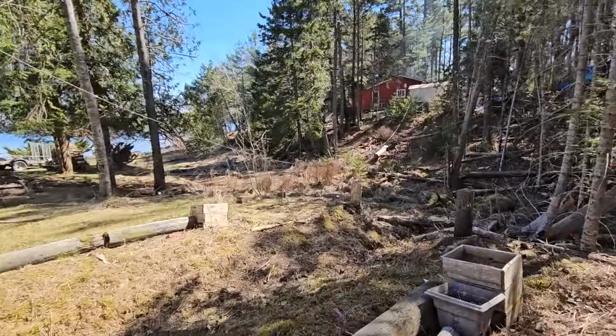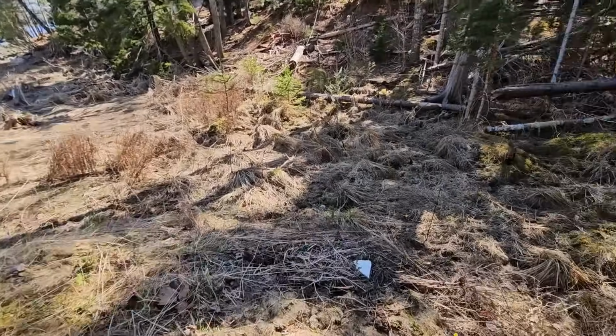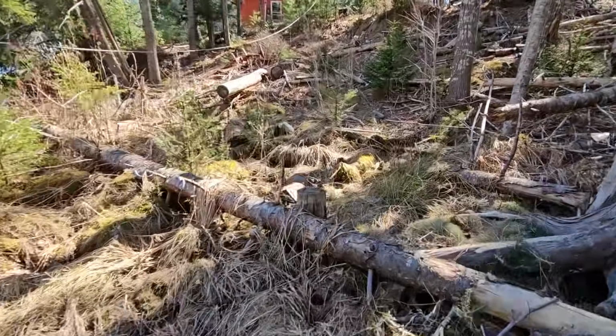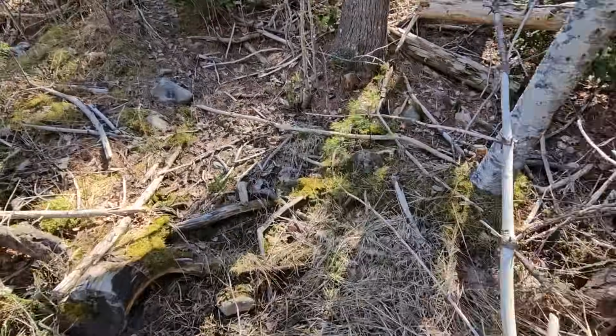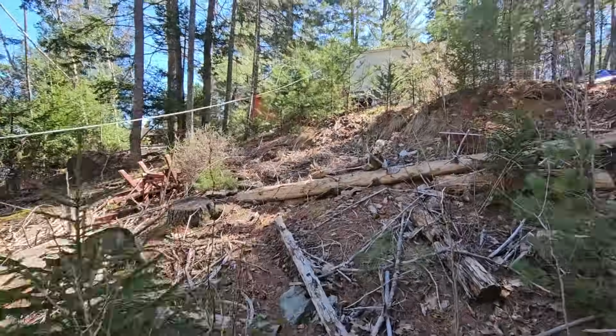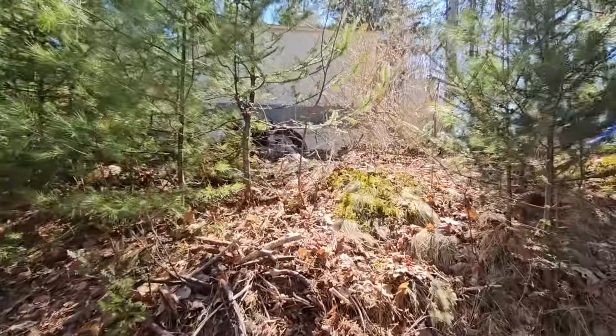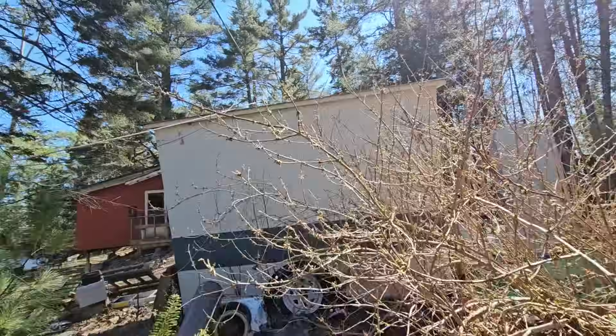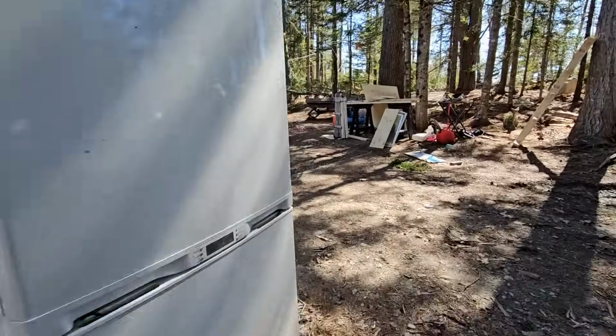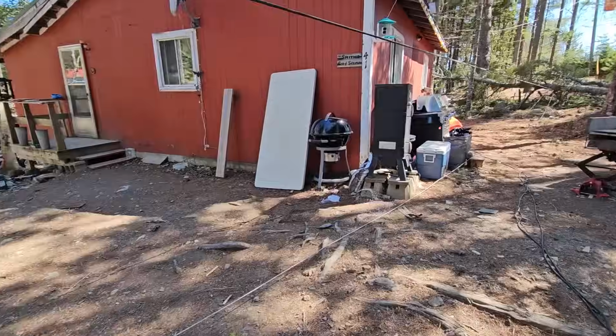So this primary wire is grounded now. A little bit of a swampy area here. That's the neutral wire on the ground right there. There's something I want to show you guys up on this other pole. That was part of our plan, part of our tailboard here. You can see that telephone way down. Let's take a look at the tree here. The break was right at the pole, so this primary is all still grounded.